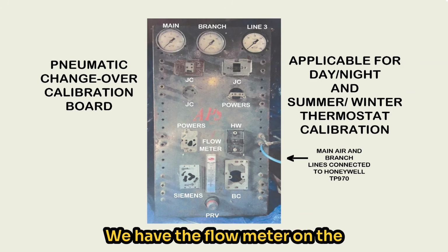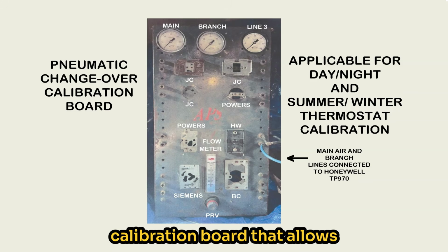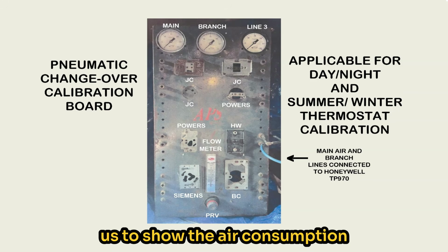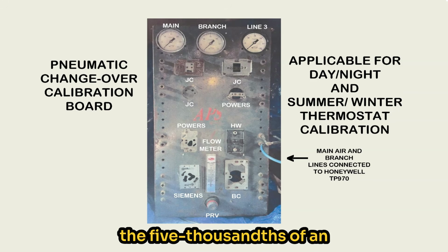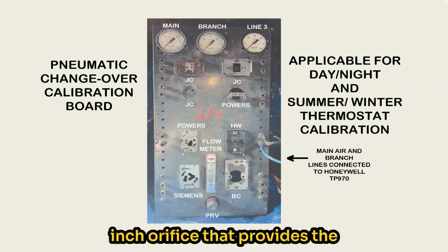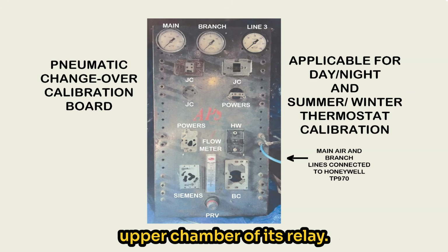We have the flow meter on the calibration board that allows us to show the air consumption of the thermostat through the 5/1000th of an inch orifice that provides the upper chamber of its relay.